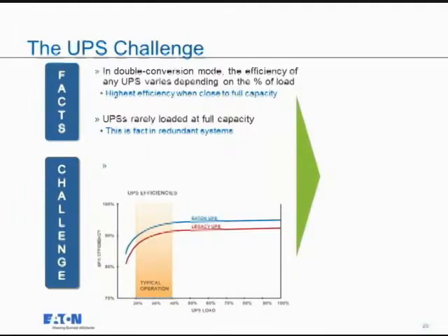Likewise, with things moving around, I often find my operations operating in small designs. I did an application a long time ago for one of the banks here in Mississauga. At the time, I think the loads were something on the order of about 200 kVA, but they were going to grow. And remember how I started the presentation. We used our best guess at future growth, and we put in a 1.5 megawatt system. Right? They felt they'd grow into it. So we built the infrastructure around 1.5 megawatt, figuring it would operate at a 1 megawatt N plus 1.